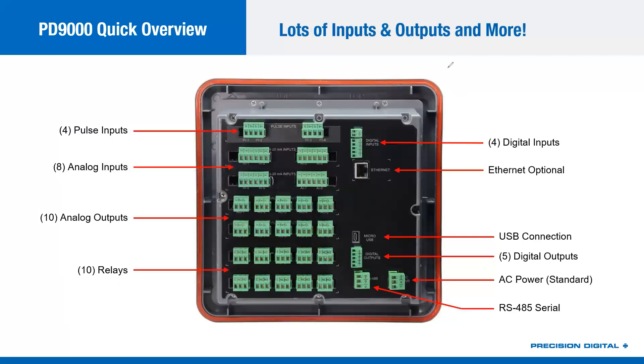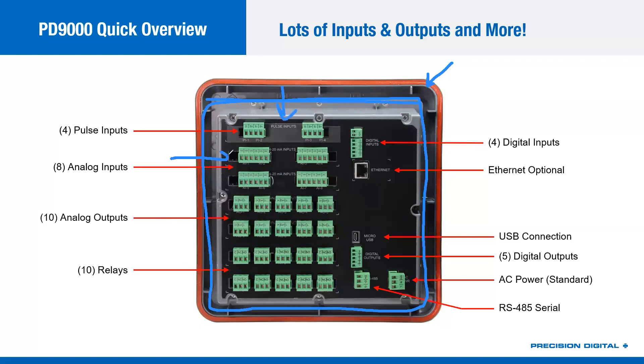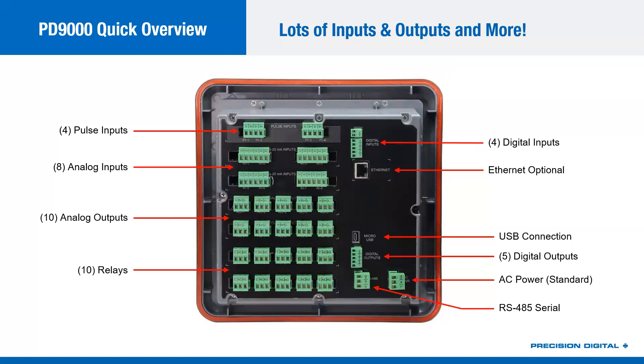Here's what a rear picture of the Consolidator Plus looks like. The gasket seals to your panel, and sticking through the back you would see just the inner rectangle area. This is an example fully populated with all sorts of different I/O. You can see pulse inputs and analog inputs — each analog input has three terminals because each analog input and each analog output has its own isolated 24-volt power supply. Every analog input or output has its own isolated power supply to run the transmitter or the 4 to 20 milliamp output loop. If you connect four level transmitters, you'll have four power supplies to run them — a great feature that saves time and hassle.